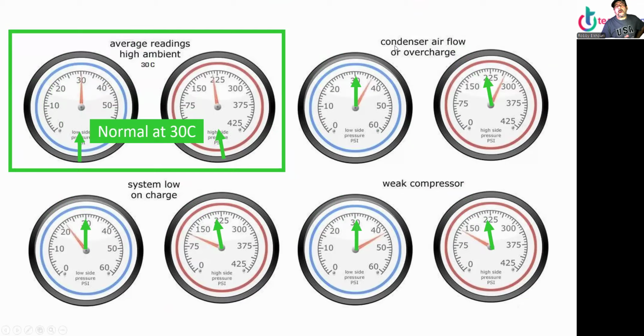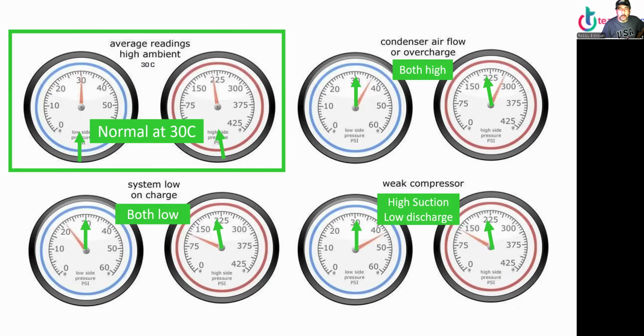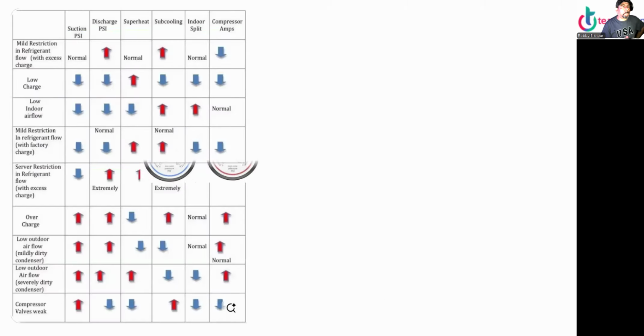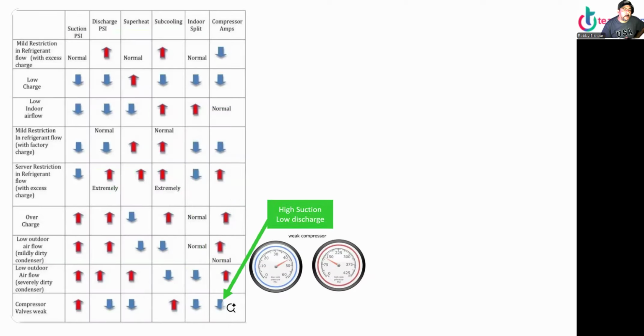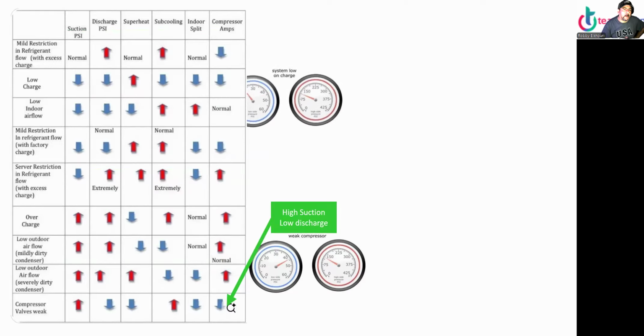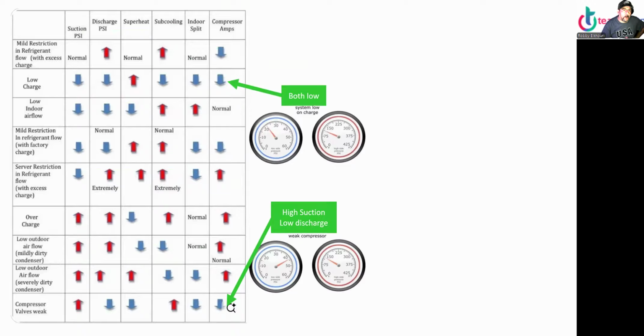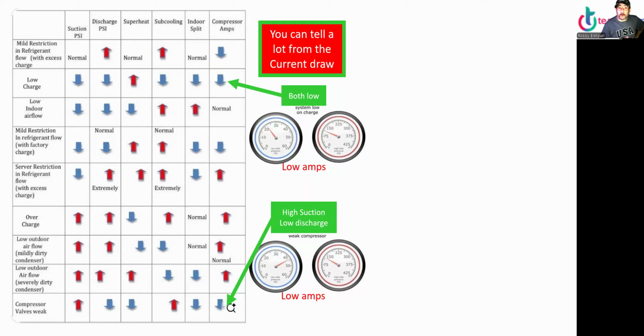All right, so here on the left, we have condenser airflow or overcharged, and both pressures are high. System low on charge, both pressures are low. And weak compressor: high suction, low discharge, weak compressor. But you've got to look at the amp draw to make sure. Now, we have a lot of arrow charts. There's your weak compressor. And look at your amp draw. Low suction and low discharge, both low. So check it out here. The low pressure is low, and the high pressure is low, and we have low current amp draw. Down here, high pressure is low, low pressure is high, and we also have low amperage because the compressor is not pumping. Low amperage, low amperage. You can tell a lot from the current draw.